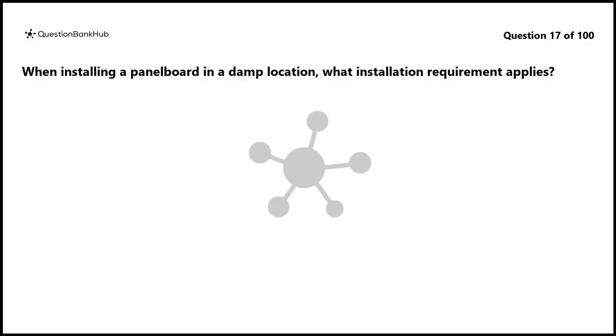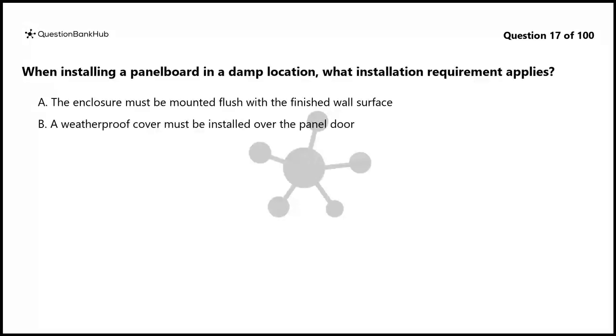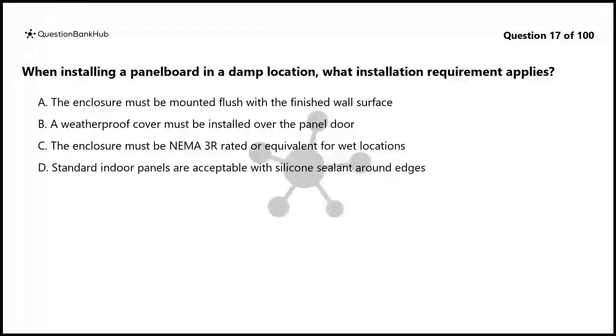Question 17. When installing a panel board in a damp location, what installation requirement applies? A. The enclosure must be mounted flush with the finished wall surface. B. A weatherproof cover must be installed over the panel door. C. The enclosure must be NEMA 3R rated or equivalent for wet locations. D. Standard indoor panels are acceptable with silicone sealant around edges.